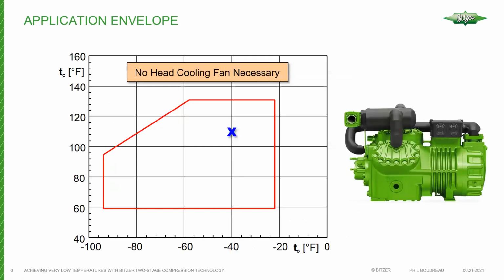If we take these same conditions now and just exchange the compressor for a two-stage compressor, this is what we're looking at now. So we have the envelope, where I like to call the operating envelope the sandbox for the compressor. In this case, you can see where the blue X indicates the operating condition. And you can see we're well inside the envelope with no head cooling fan required in this case. Although there's auxiliary cooling, interstage cooling, which we'll talk about.